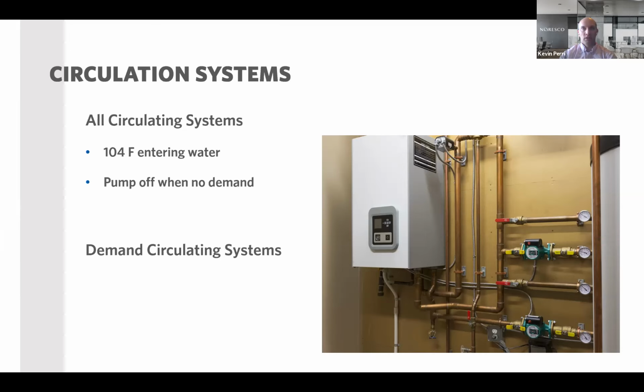I see some potential issues with that, but it's not my place to go into that during this conversation, but there could be some workarounds here that are not great for energy efficiency. And then the pump needs to be turned off when the desired temp loop has reached the desired temperature. So basically, if you're trying to have a 130 degree loop temp and there is no demand for water, then that circulation pump needs to turn off.